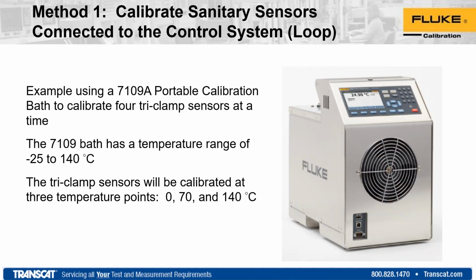All right, so we're moving into example one, using just the bath with a connected, or what they call a loop calibration test. We're going to state for this that we're going to use the TriClamp sensor. We're going to pull it out of the process that it's in, and we're going to test it at 3 points, say 0, 70, and 140 in the bath, but we're going to leave it connected to the control loop at the control board. So again, we're not removing it completely, just from the pipe that it's at.